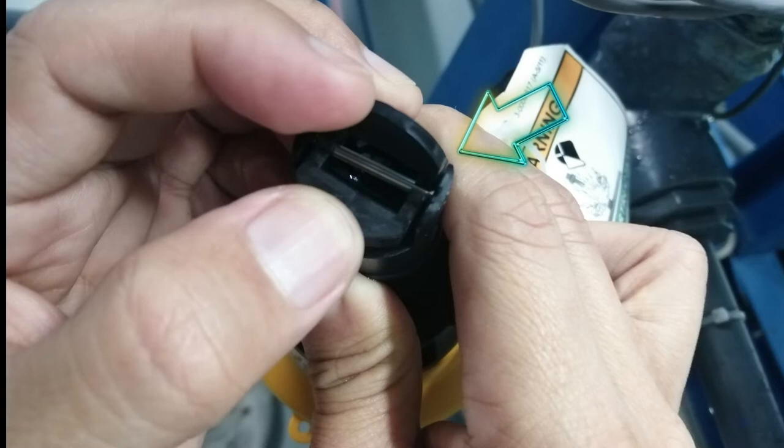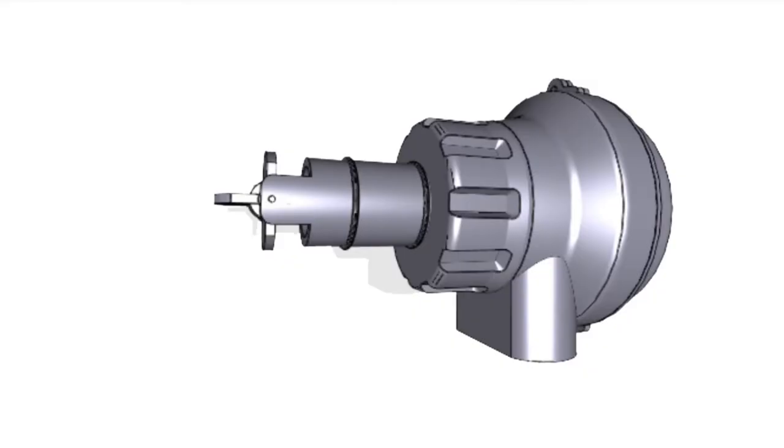From the number of revolutions, the paddle wheel was broken. That's why there was no reading of GPM in the HMI.